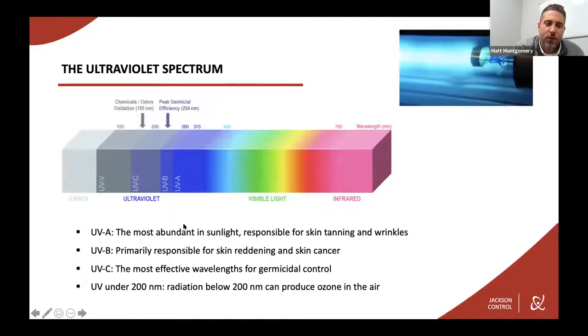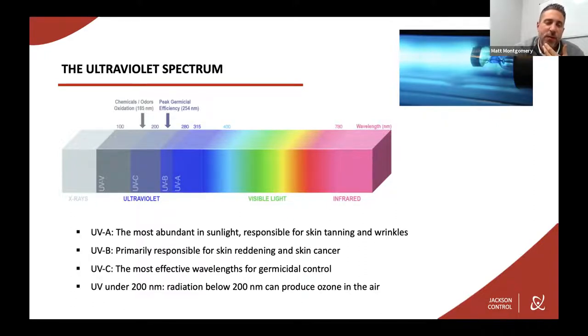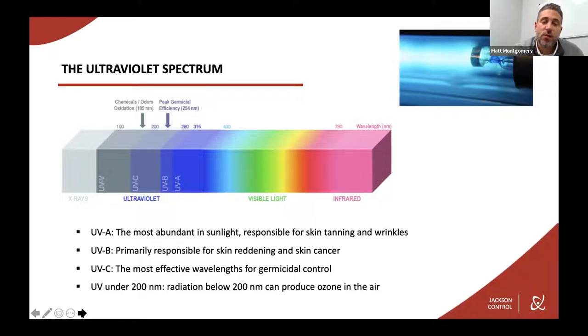A high-level overview of the electromagnetic spectrum as it relates to ultraviolet rays and sanitation. UV light covers a wavelength spectrum from 100 to 380 nanometers, subdivided into three regions. UVA is about 320 to 400 nanometers — the most abundant UV in sunlight, responsible for skin tanning and wrinkles. UVB is 280 to 320 nanometers, primarily responsible for skin reddening and skin cancer. UVC is 200 to 280 nanometers and is the most effective wavelength for germicidal control. Any UV under 200 nanometers can produce ozone when introduced with oxygen.